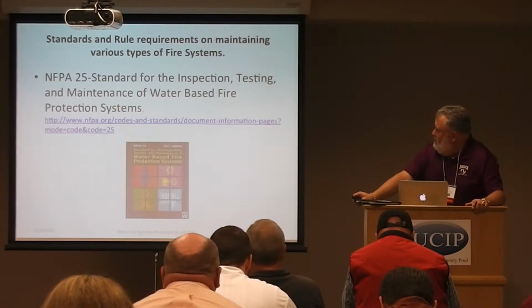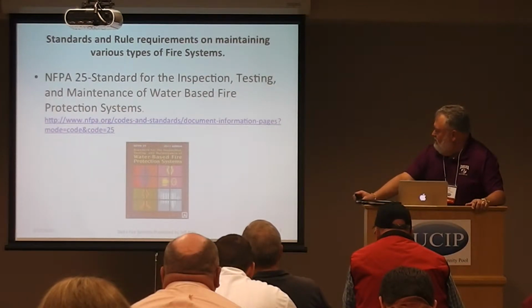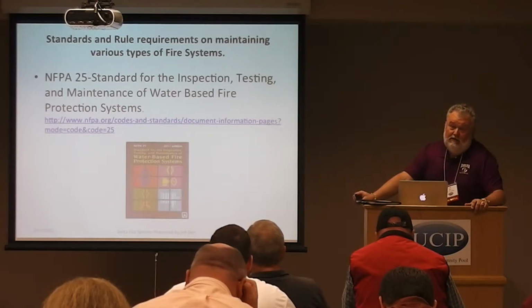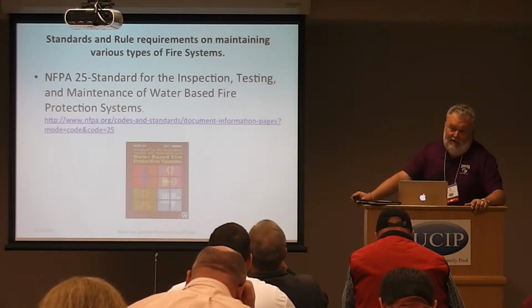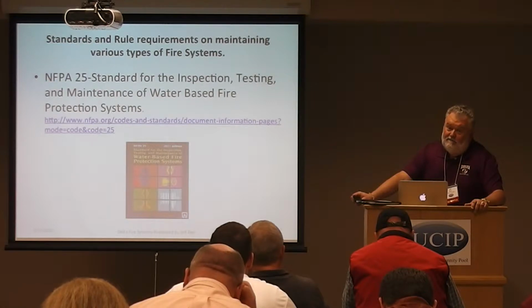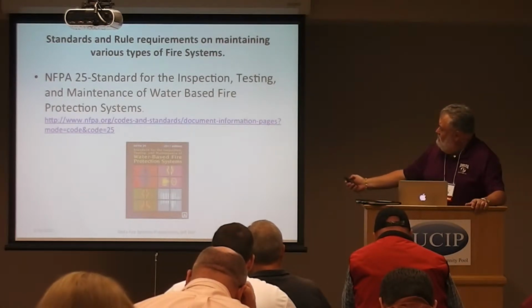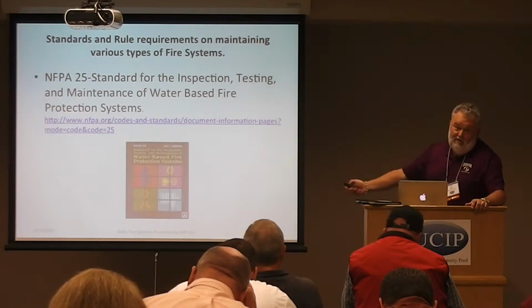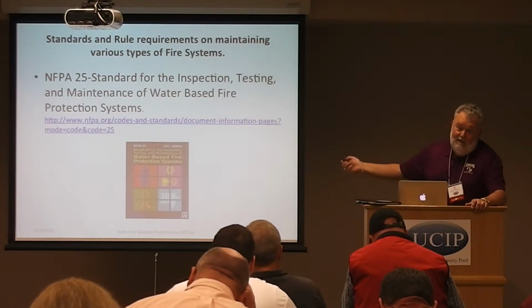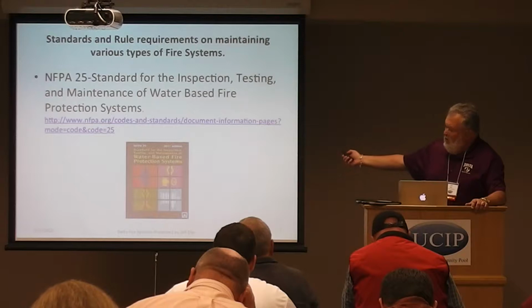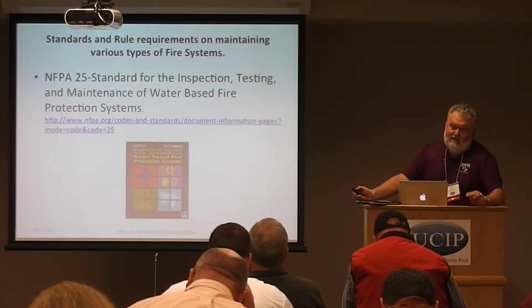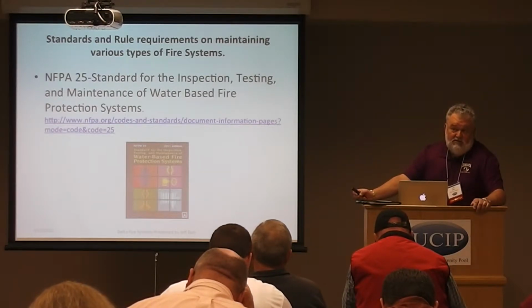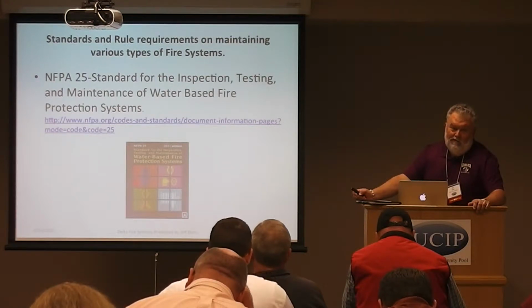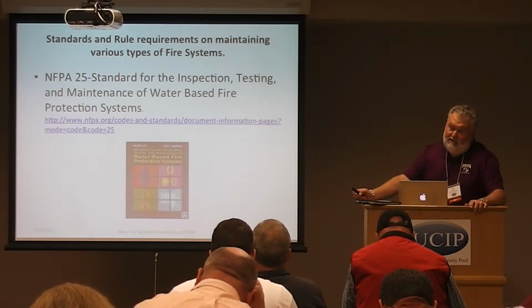Now, here is the NFPA 25. There's a link to it. Again, that's what we live and go by in the state here. And so if anyone says they're doing a proper inspection for you, make sure that they're enforcing and going by this standard. Now, this standard assumes that the system, once it's installed, was installed correctly for the code it was under. So it's kind of a nebulous area there.